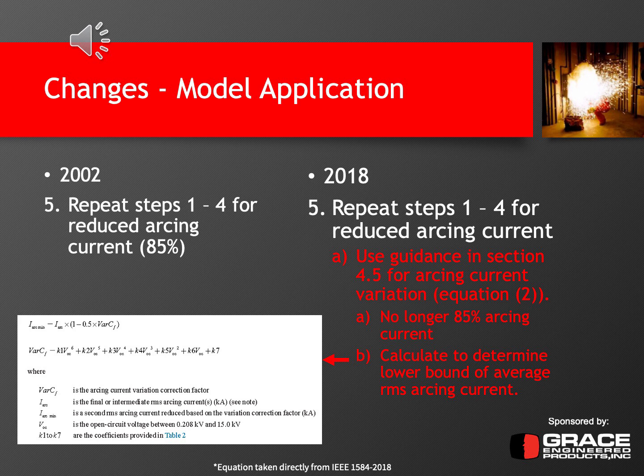So in 2002, it was just rerun the same calculations with the arcing current reduced to 85% of the calculated value. While in 2018, you would need to use the guidance in section 4.5 for arcing current variation, which is equation 2. So it's no longer, like I said earlier, the 85% arcing current value. You now need to calculate the lower bound of the average RMS arcing current. And that equation is shown here in the bottom left as IARC min. And there's also a variable, or correction factor, which is the arcing current variation correction factor.